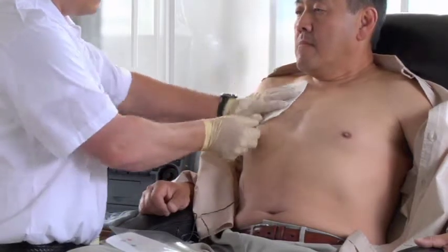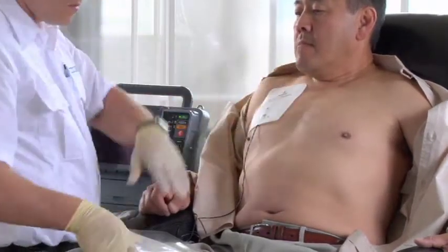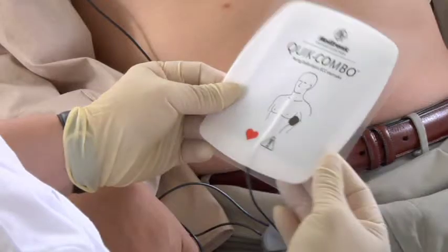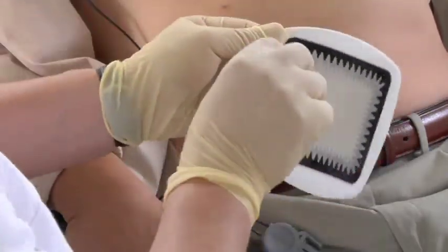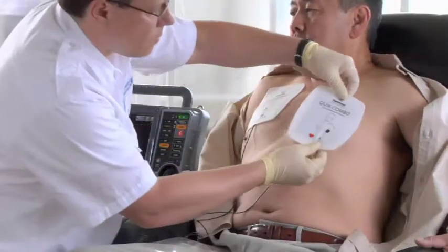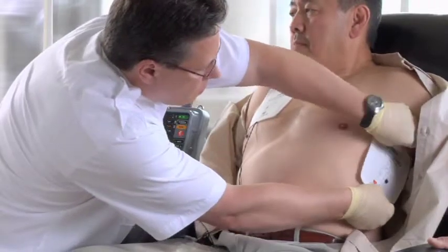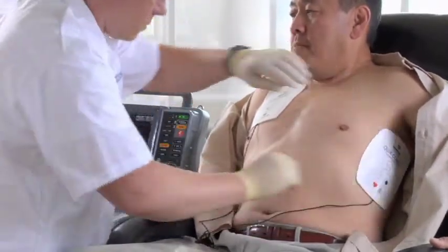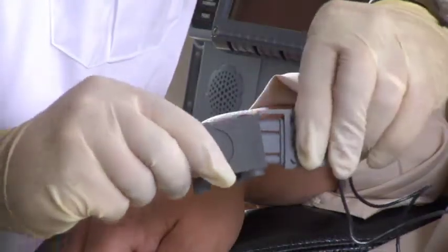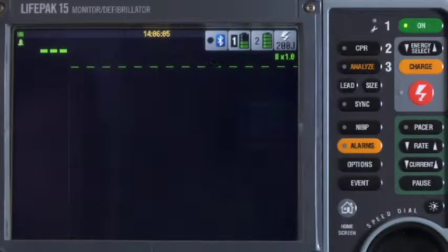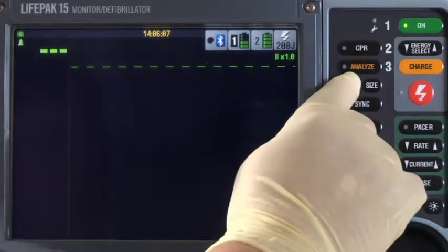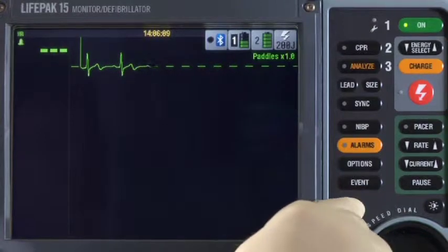Press it down firmly to get good contact. Place the other electrode under the arm. Place it lateral to the patient's left nipple in the mid-axillary line. Connect the therapy electrodes to the therapy cable. If you don't see an ECG, you need to switch to paddles lead. Press lead once, and it will automatically change to paddles lead.